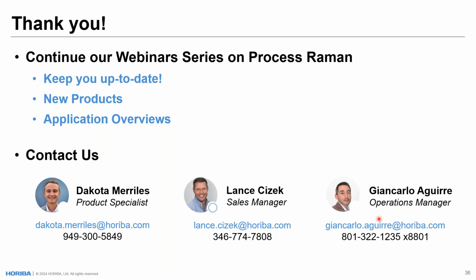All right. The next one would be, what is the lifetime of the laser? That's a great question. In a situation where the laser isn't running all of the time, the lifetime is greatly extended. For example, with the redundant lasers of the online systems, we like to say that the average lifetime is about 3 years. In the laboratory analyzers, where the lasers wouldn't be on all of the time, it would be about double that, so about 6 years for a lifetime of the laser. Something else I'd like to mention about the lasers is we purposefully design them to be plug and play, so there's no alignment or calibration needed when a laser goes down and we send you a new one. There's only 3 things you have to plug into the laser at a time. That is helpful when a laser dies and you need an emergency replacement from us, and we can send it to you.